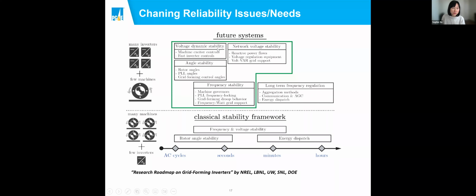of the inverters in the future to control the voltage, terminal voltage, and to maintain stability of control during system disturbance. And the next one is more about the classic voltage stability that we're studying in the system, reactive power flows, and potential voltage collapse issues, and those kind of network related issues. And long-term, obviously a little bit longer, after a few cycles upon clearing the fault, the frequency stability, the frequency regulation, goes hand in hand and is also a big challenge when we have more renewables and less synchronized machine.